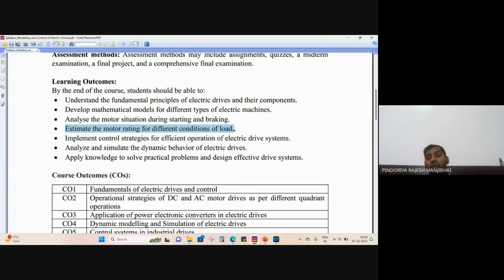That's why transformer rating is kVA, because we don't know which type of load the customer will connect, maybe inductive, maybe capacitive. So it's always rated in kVA. But for a motor, it doesn't depend on the power factor because we only connect a mechanical load, so it's not dependent on power factor.